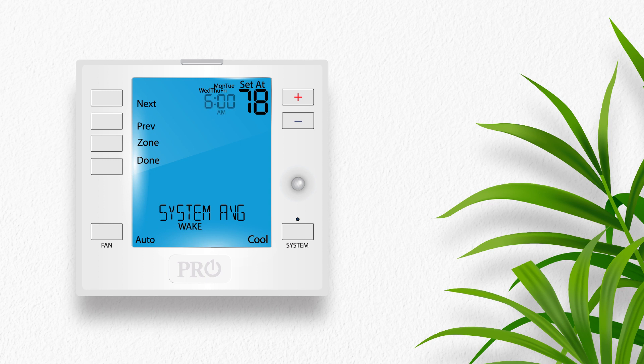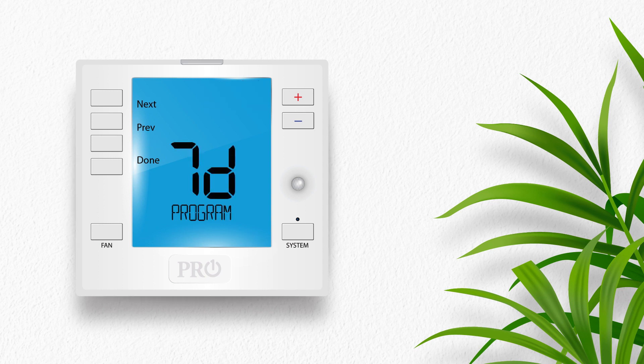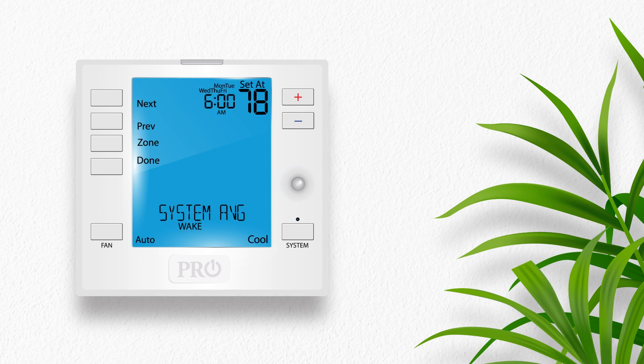If you would like to program every day individually, go to the tech setup menu and choose the seven-day option. When entering the menu, the thermostat will display Monday through Friday at the top and the wake icon, indicating that you are now programming the wake time period for all weekdays together. With the time flashing, use the plus or minus buttons to select the time you would like the wake time period to begin for Monday through Friday. You can also set the fan operation for each time period.